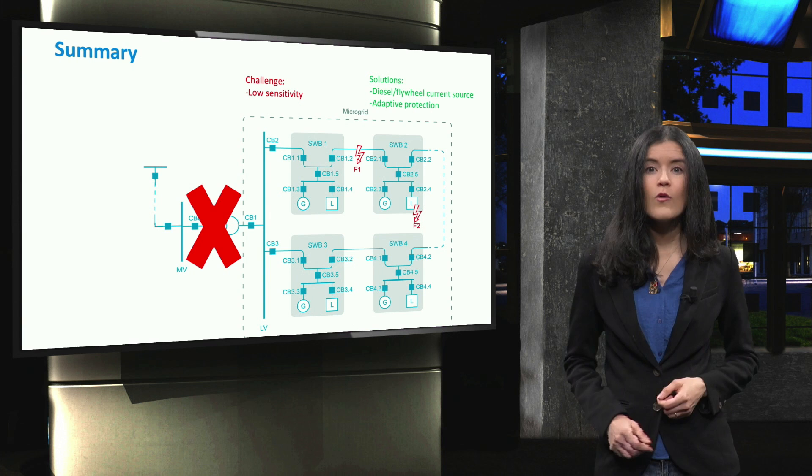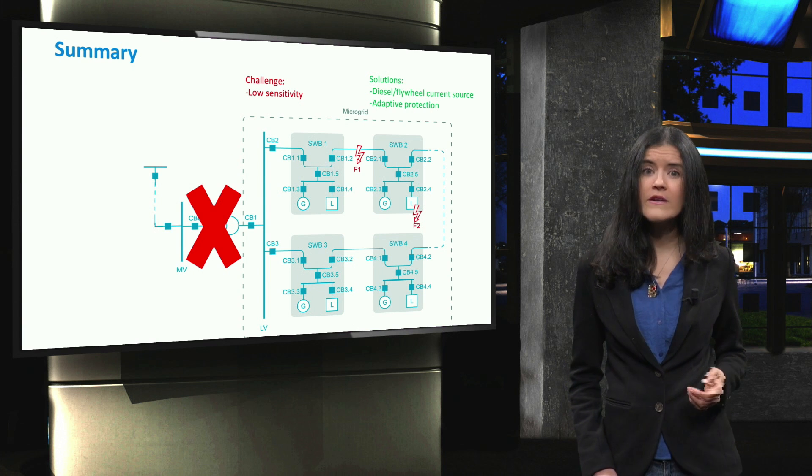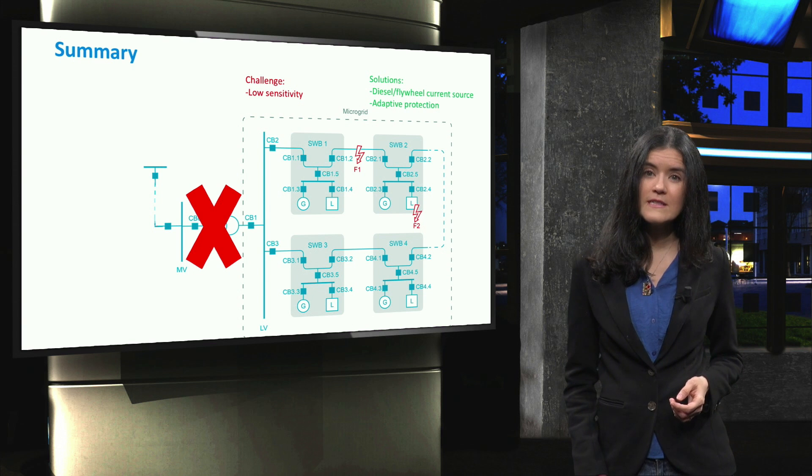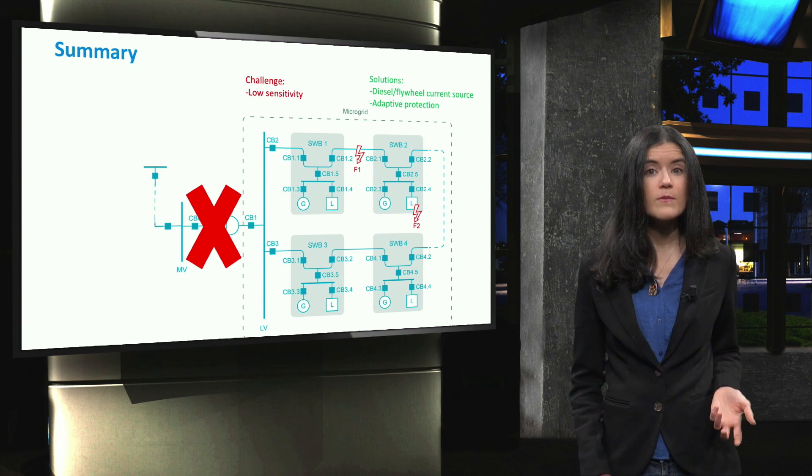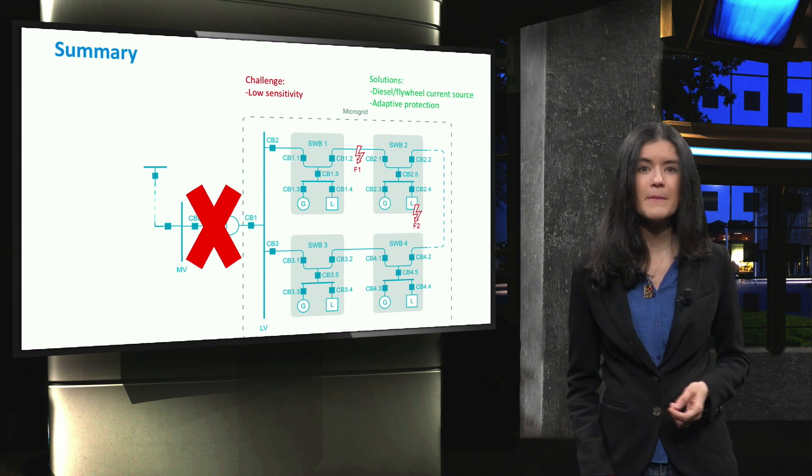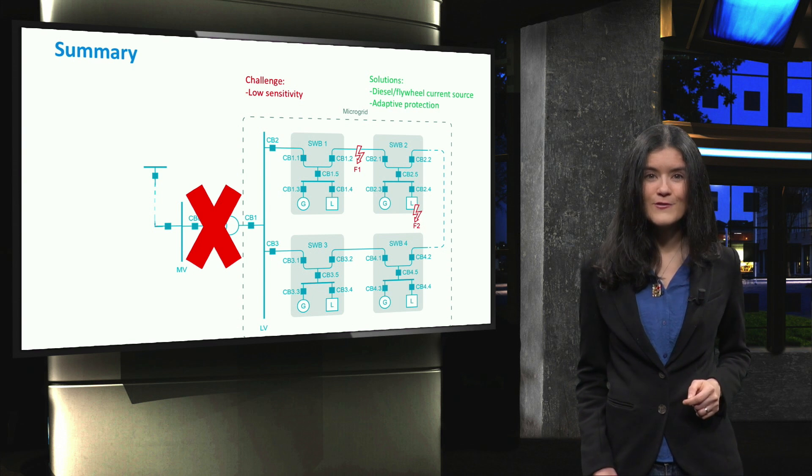In summary, we have seen in this video how microgrid protection works in islanded mode. To tackle the low sensitivity challenge faced by the conventional protection schemes, an adaptive protection scheme is sometimes implemented, as we will see in the next video.